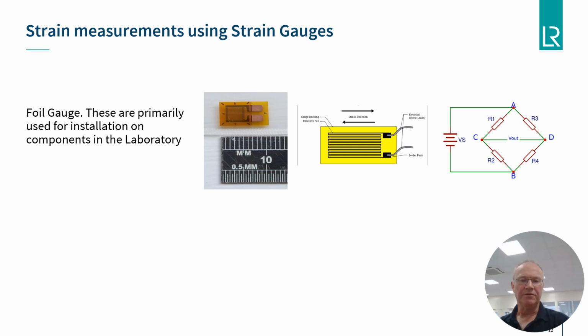These devices are bonded to a surface, usually with an adhesive, and give a change of electrical resistance proportional to the change of the surface strain. If compressed, the resistance reduces, and if pulled in tension, the resistance increases. When strain gauges are connected in a Wheatstone bridge configuration, as in the right-hand image, they can be connected to strain gauge amplifiers or conditioners and subsequently recorded with data acquisition equipment.